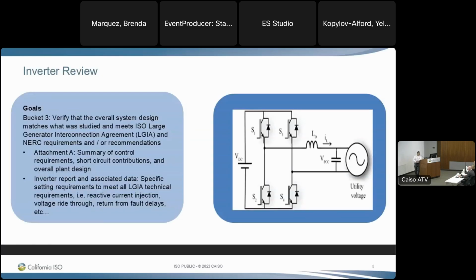Inverter review. This can be a little bit more complicated. The LGIA is very specific in performance reviews on what we look for out of the inverters. It's a performance-based standard. It also talks about reactive current injection. The attachment A has a summary of those control requirements, the short circuit contributions, and an overall plant design.